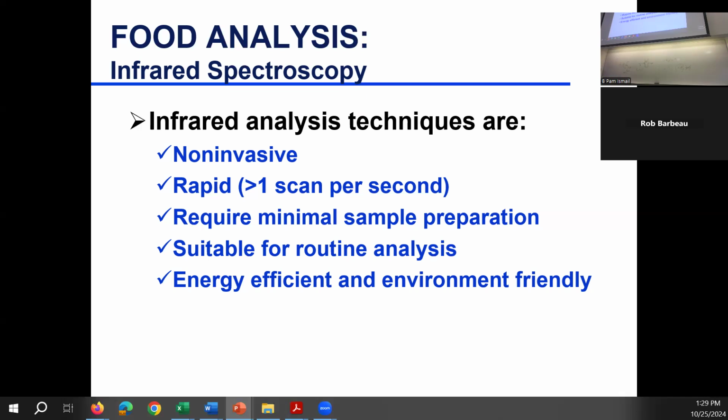It's very, very rare that you have a background. There's background noise that you would calibrate the equipment itself with 0% transmittance and 100% transmittance. But your sample usually doesn't have any reagents, so there's no blank that you would have to prepare. Usually the blank that we use to zero the instrument is made up of the reagents you use to prepare your sample. But here you have, let's say, grain or milk. There's no reagent as is, you measure them as is. So you only try to calibrate for the instrument noise.